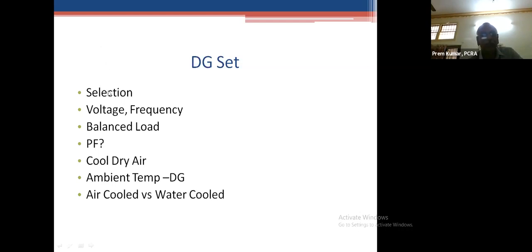So voltage is very important. Ensure that you get a balanced voltage. Frequency when read at 49 is okay. Need not increase it to 50 cycles per second or 50 hertz. Balance loads. So this is very important. Many times companies resort to power factor improvement only for the transformer area. When they run DG, they forget it.